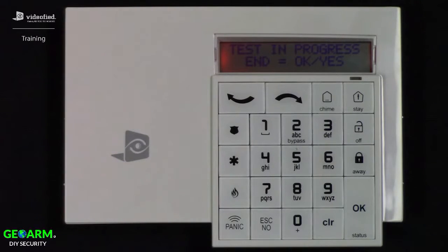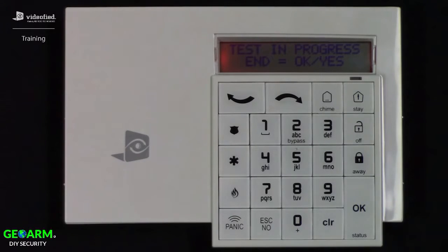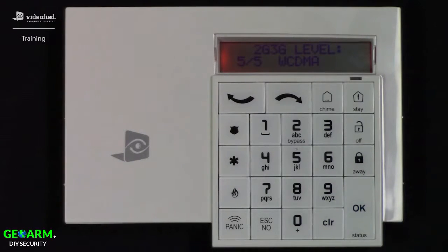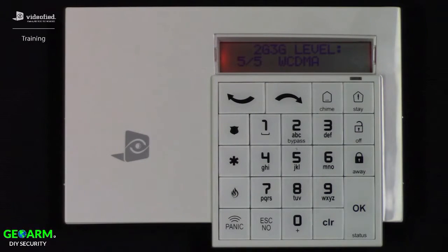Once this test has been initiated, please keep in mind that it can take approximately 30 seconds up to 2 minutes before it will return its final result. During this time, if the test appears to be taking longer than 30 seconds, go ahead and press one of the number keys or arrow keys to prevent the keypad display from turning off. Once the system displays its final result, it is recommended to allow the system to rest on that screen for an additional 30 seconds to confirm there is no fluctuation in the cell signal.